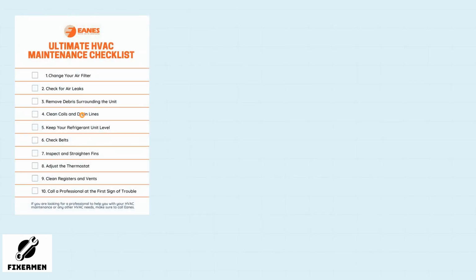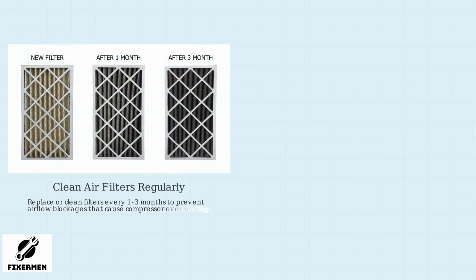HVAC experts emphasize that most E4 errors stem from user-side issues like poor maintenance. According to a 2025 survey, 70% of E4 errors come from preventable causes such as neglected upkeep. One of the most important preventive measures is to regularly clean or replace air filters. Dirty filters restrict airflow, forcing the compressor to work harder and potentially triggering the E4 overheat error. Experts recommend checking filters monthly and replacing them every 1 to 3 months, depending on usage and air quality.